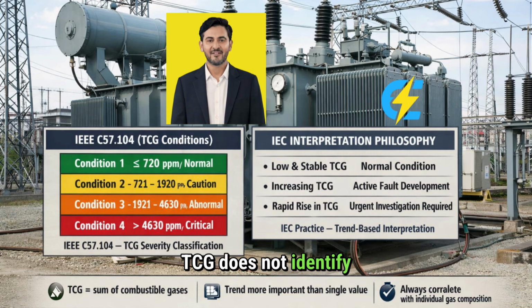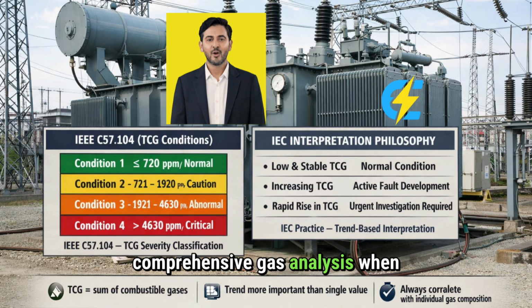TCG does not identify fault type. That's the job of individual gas analysis and ratio methods. TCG is fundamentally a risk management tool, not a diagnostic tool. It helps you prioritize your resources and make informed decisions about transformer operation, but it doesn't replace the need for comprehensive gas analysis when determining the specific nature of a fault.